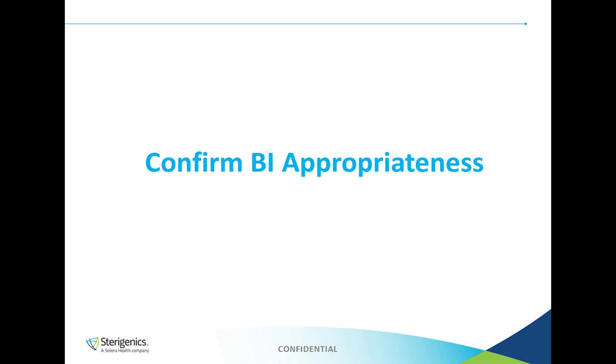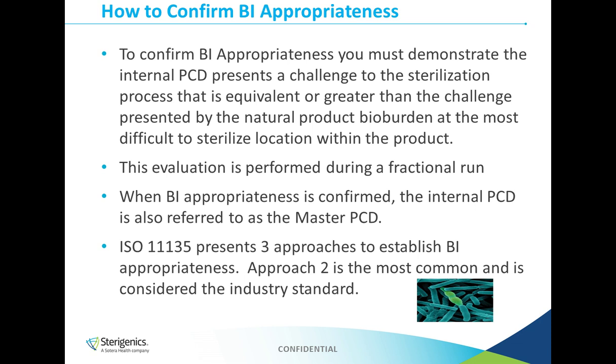So now that we've got the first objective out of the way, let's go ahead and talk about the second one, which is to confirm BI appropriateness. To confirm BI appropriateness, you have to demonstrate that the internal PCD that we just talked about represents a greater or equivalent challenge to the sterilization process than the natural product bioburden of the product in your product line. And this is at the most difficult to sterilize location.